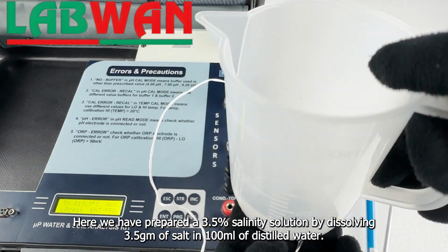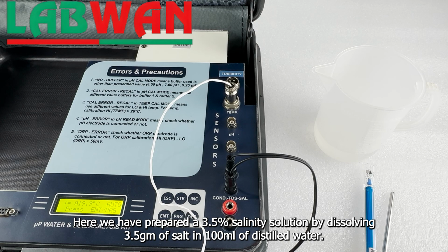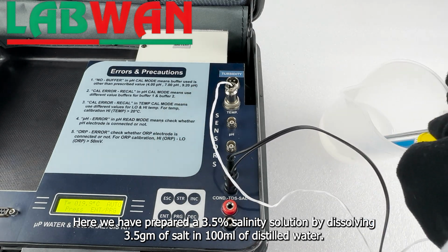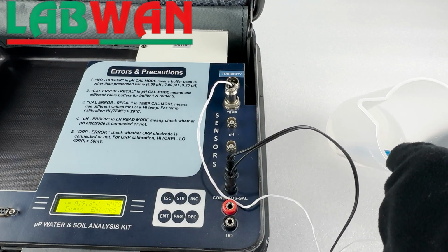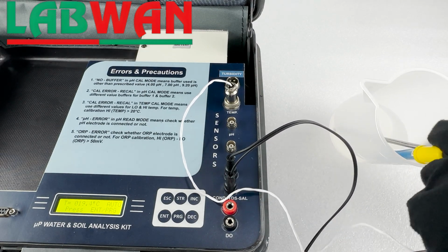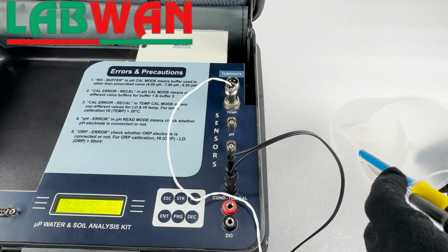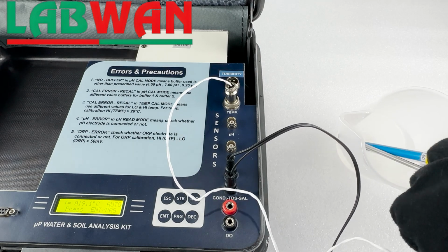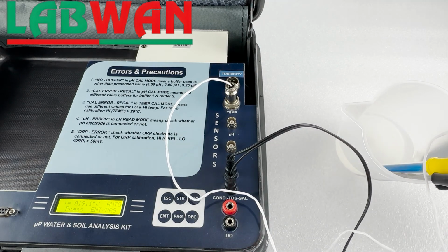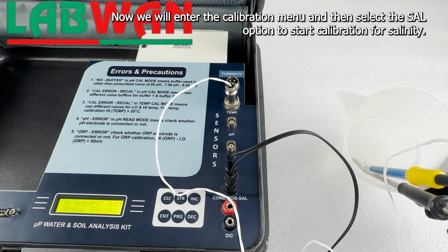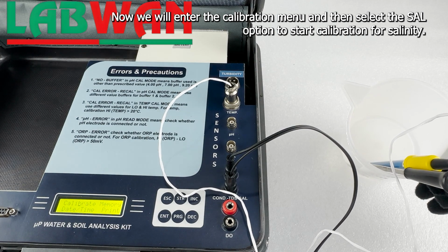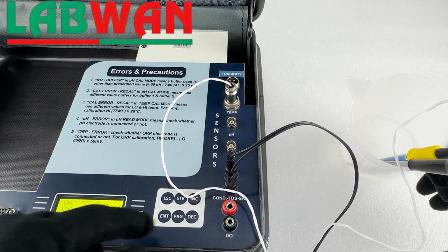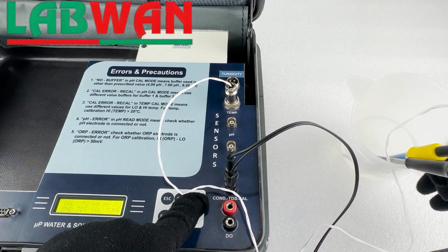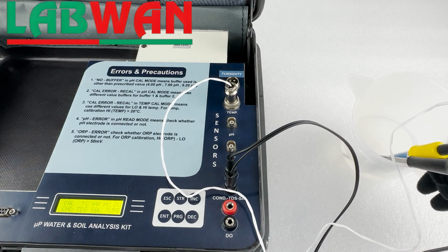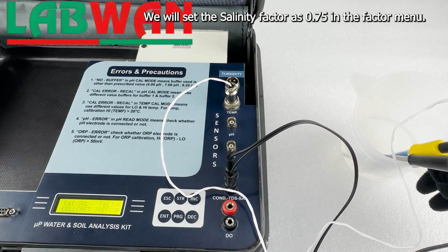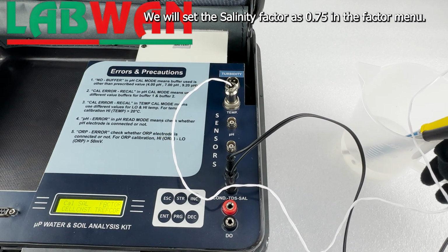Here we have prepared a 3.5% salinity solution by dissolving 3.5 grams of salt in 100 milliliters of distilled water. Now we will enter the calibration menu and then select the SAL option to start calibration for salinity. We will set the salinity factor as 0.75 in the factor menu.